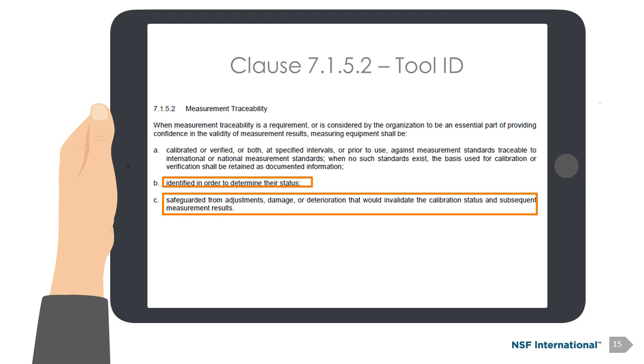And when no standards exist, the basis for that calibration or verification needs to be retained as documented information. So essentially, we're going to do it to the standards that have been derived from some national science institute, or NIST in our case, or whatever national equivalent there might be. Or if there's no standard that exists, we're going to come up with a method. We're going to define that method in documented information, and then we're going to have some evidence to show that that's been done.